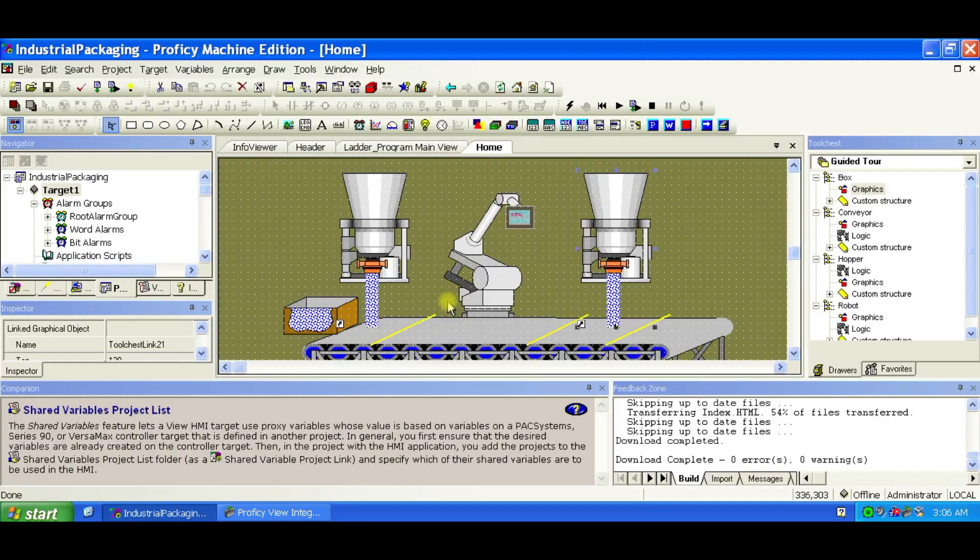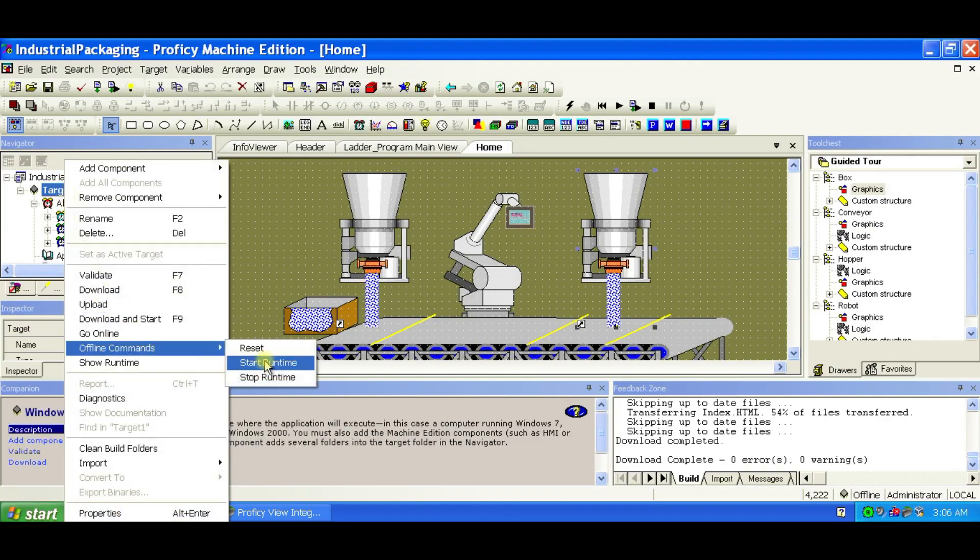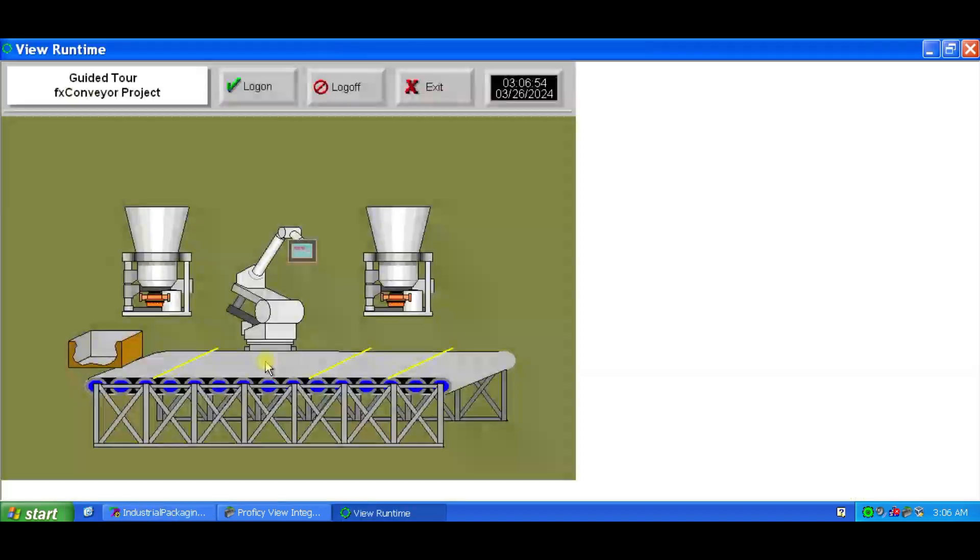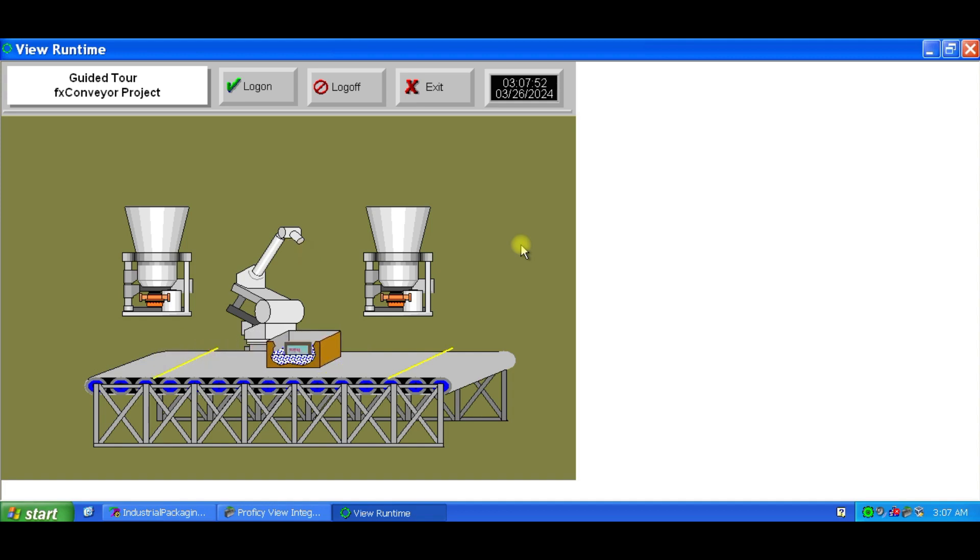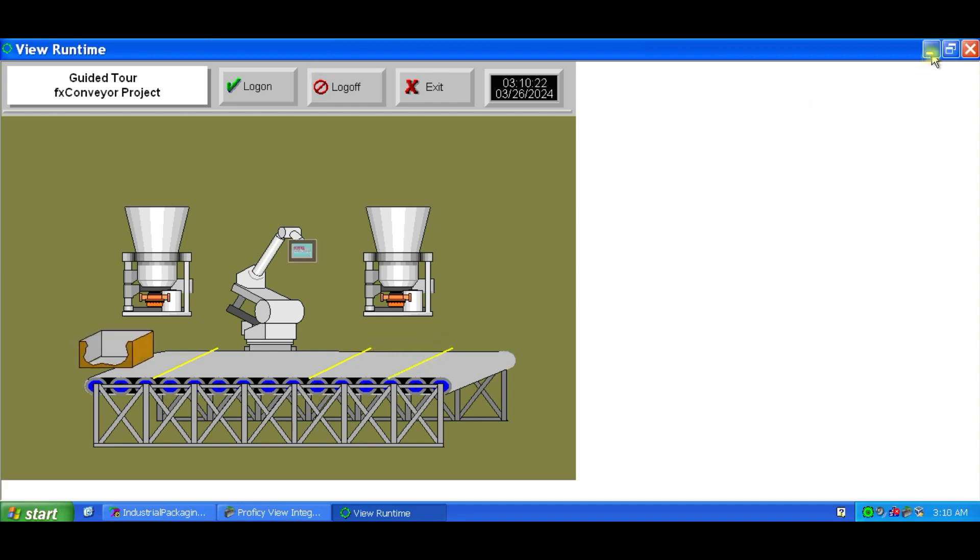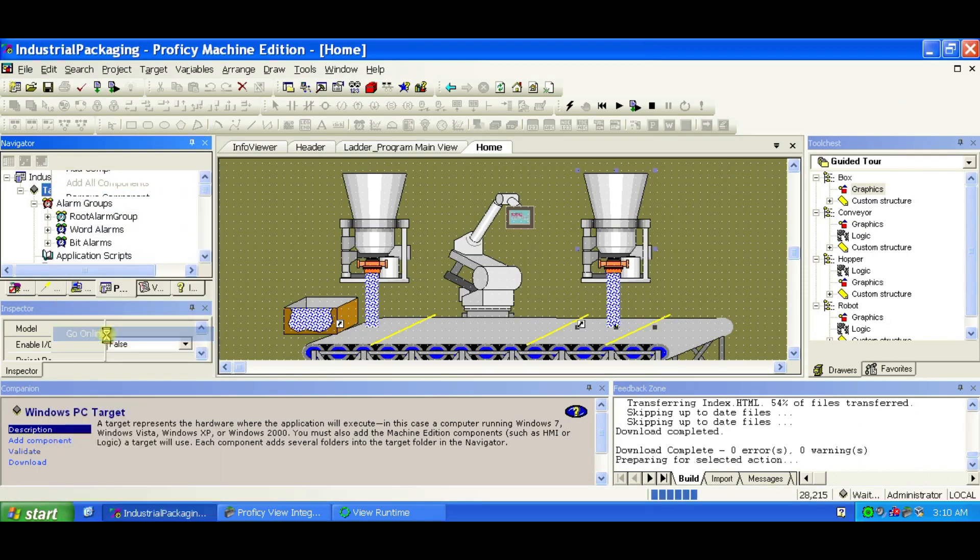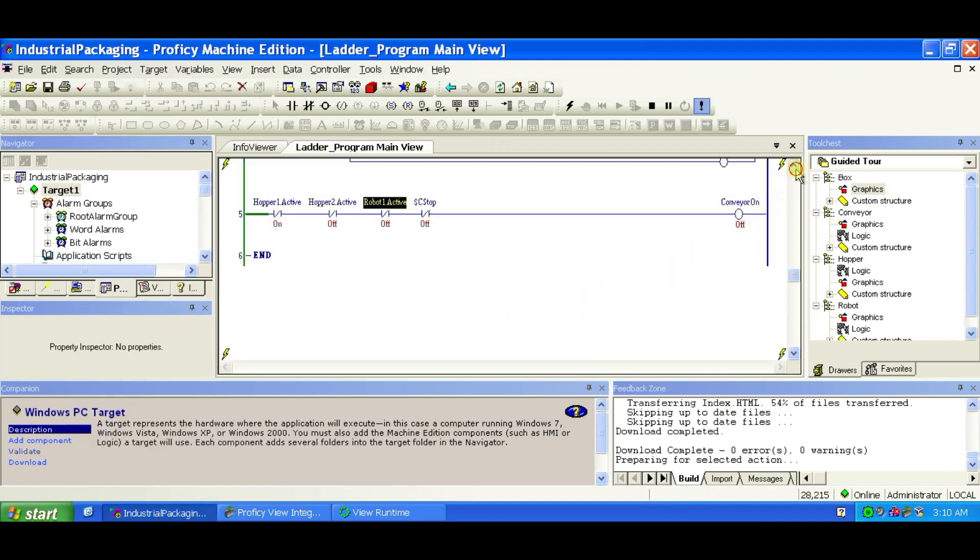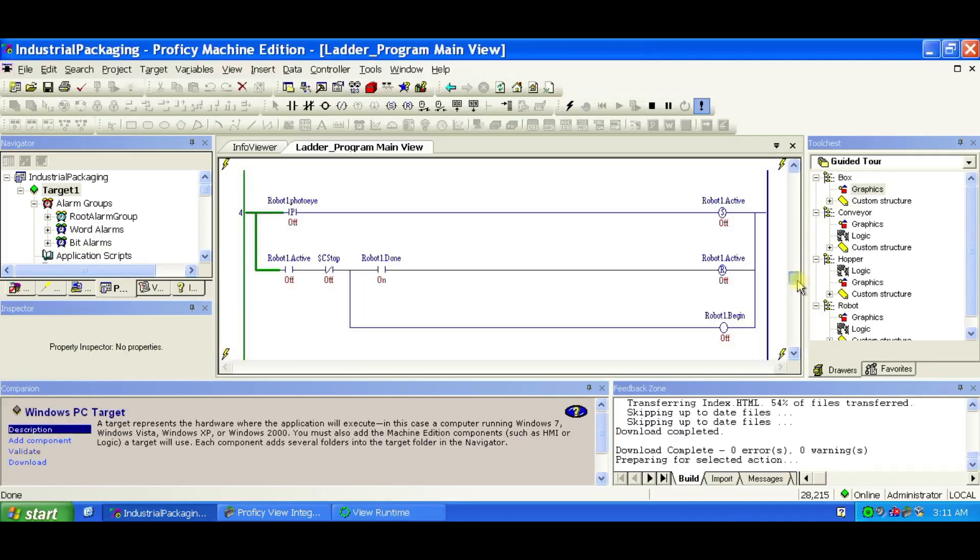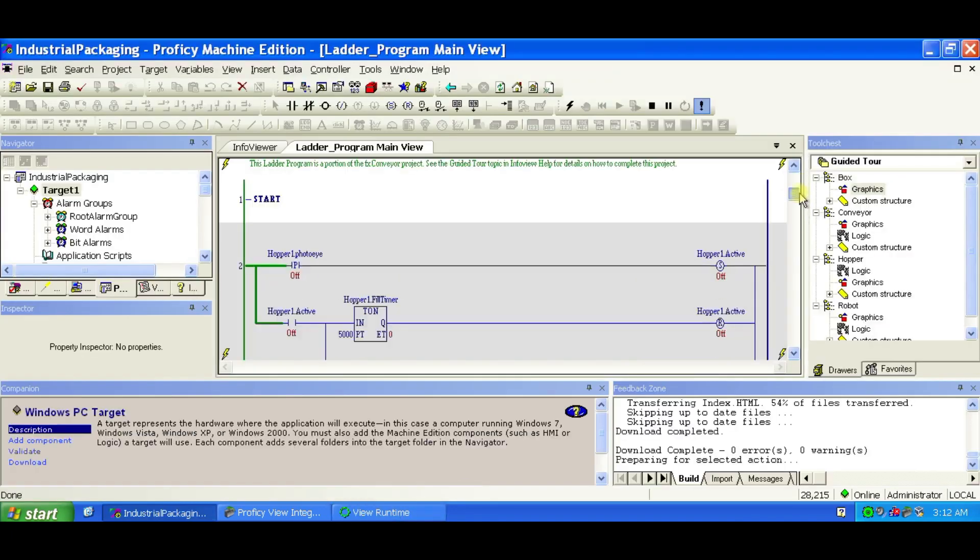You can start the View Runtime by right-clicking on Target 1 and choose Offline commands then Start Runtime. To see Powerflow and your logic, open the Ladder program. Right-click Target 1 and select Go Online. The icon will turn green, and you'll see live execution of your ladder diagram. Take time to observe the logic and monitor the runtime, it will help you understand how everything works.